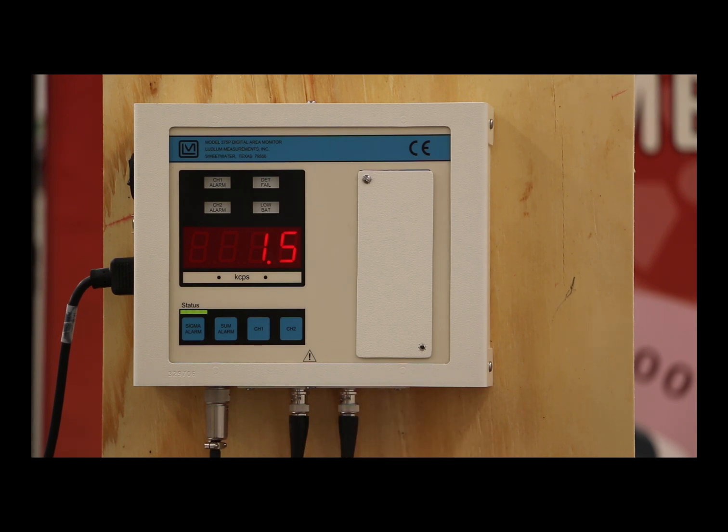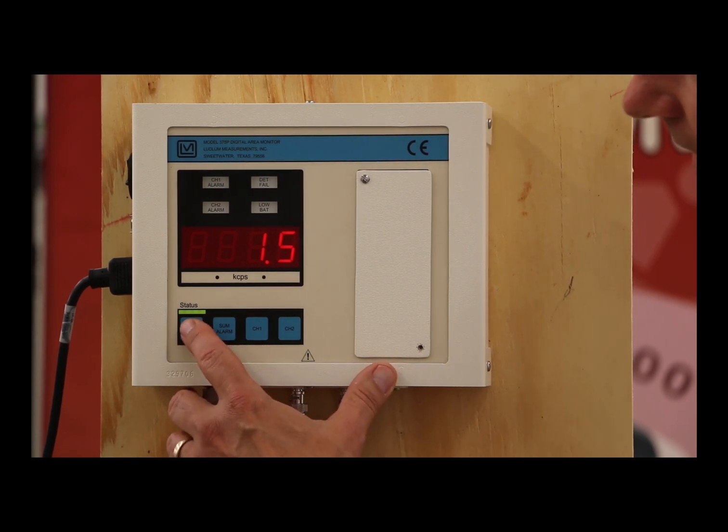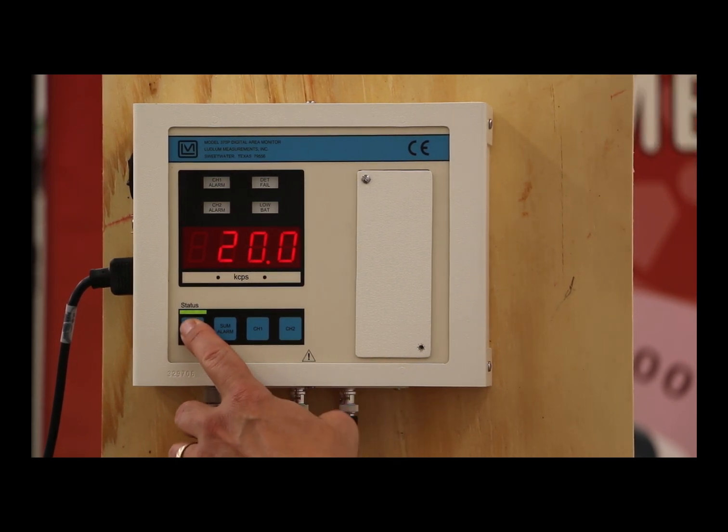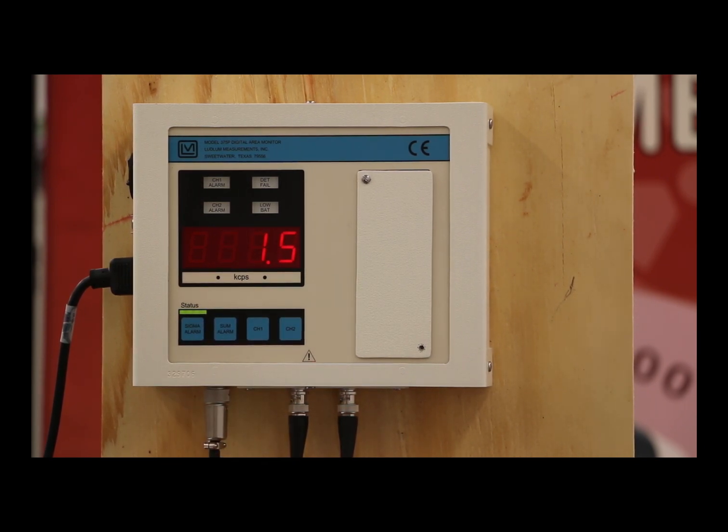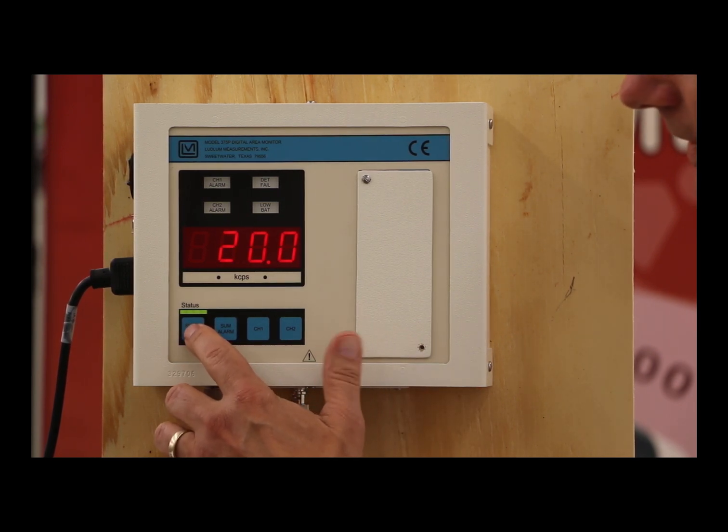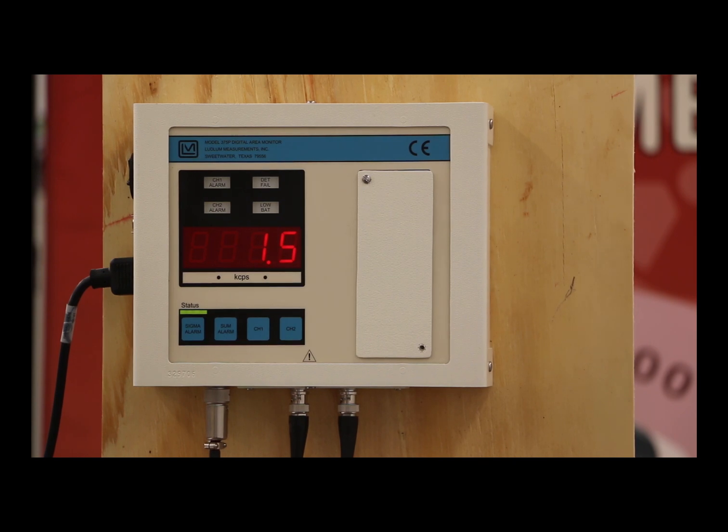So we set the sigma alarm. In this case, it's set, as I push the button here, to 20 sigma. So 20 times that square root of the background gives you my differential. Anything background plus that differential of 20 times the square root of the background would give you an alarm. That tends to be a very fast alarm, and really this is the alarm that you're going to mostly see when you're using these as a portal.